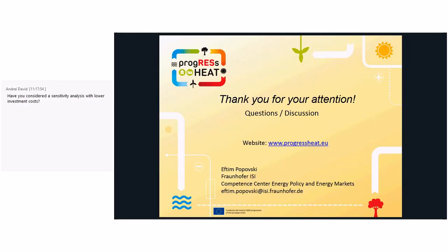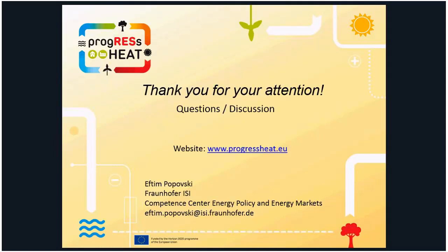Yes, we have considered a sensitivity analysis, but as mentioned before, the influence of the electricity price and the COP plays a much larger role in this case. Because of that, we focus more on how to reduce the electricity price, what the options are, and how the COP of the heat pump can be increased. In our opinion, even though we assumed a much higher investment cost, even if we reduce it based on the sensitivity analysis, it won't give us the expected results, or make the heat pump competitive just by reducing the investment costs. So this is definitely not enough.